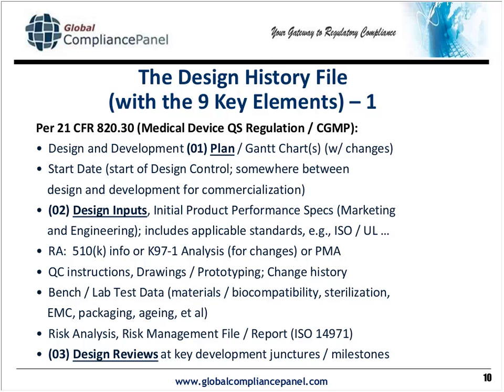I go through and pull up one of these blank matrices and fill it out to determine whether or not I have to file a new 510K as a result of one major change or a series of minor changes cumulatively considered with each new minor change, to determine when, in fact, my product has reached a point where safety and efficacy become an issue again and a new 510K has to be filed. There's another simple way to do that, and that is to take the K97 document verbatim, just print it out and annotate it manually and sign and date it. That's another way, but it doesn't fit in with electronic records if you're already under that kind of system.